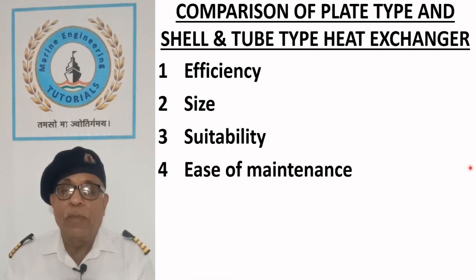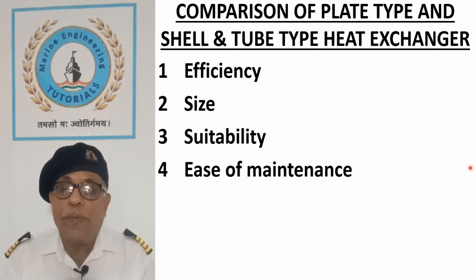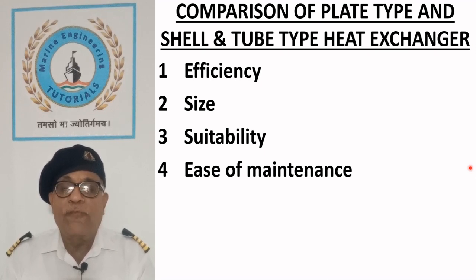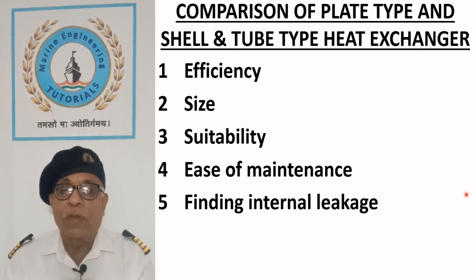Ease of maintenance. Plate type heat exchangers are easily opened and cleaned as compared to shell and tube type, which also require free space equal to the tube length on one side for their cleaning. Finding internal leakage. It is easy to detect internal leakage in shell and tube type heat exchangers as compared to the plate type cooler when a leakage develops. The plates must be visually examined to detect the fault. The joint between them can present problem in service or after maintenance.